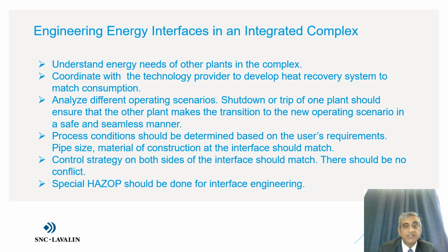Process conditions should be determined based on the user's requirements. Pipe size, material of construction, etc. should match at the interface. Most important, control strategy at both sides of the interface should match. There should be no conflict of control strategies. A special HAZOP should be conducted for interface engineering.